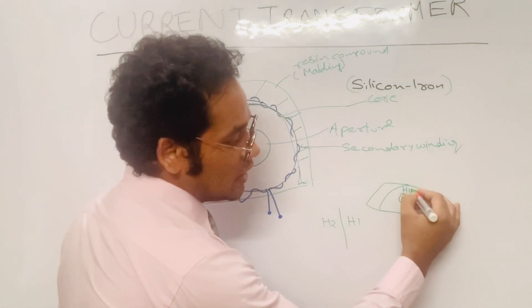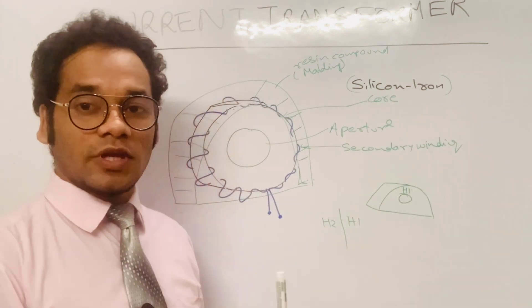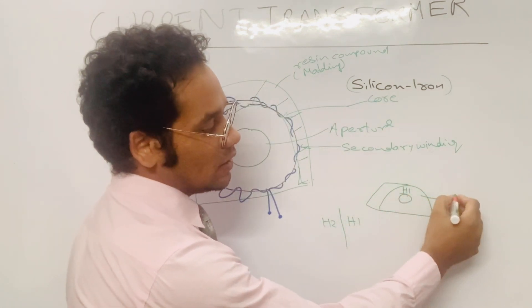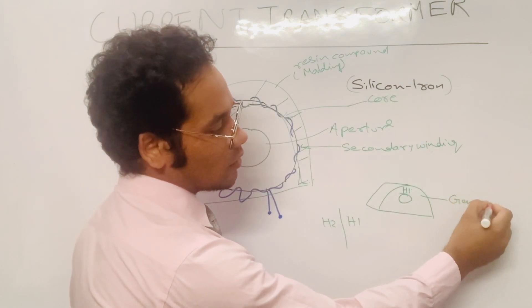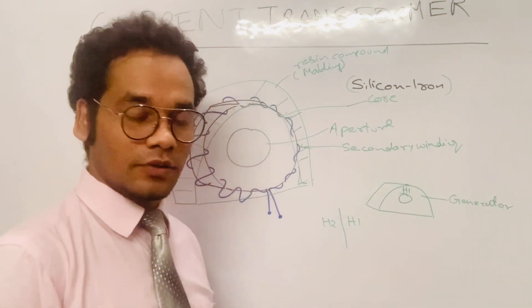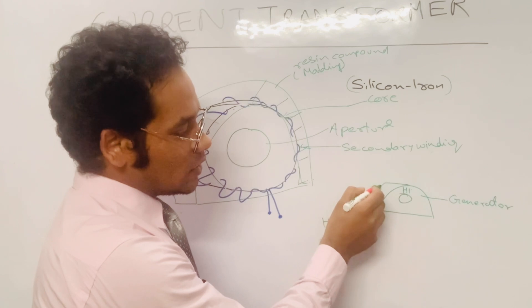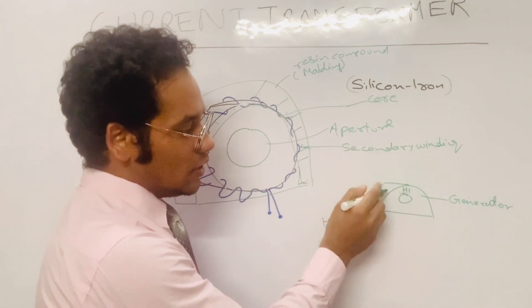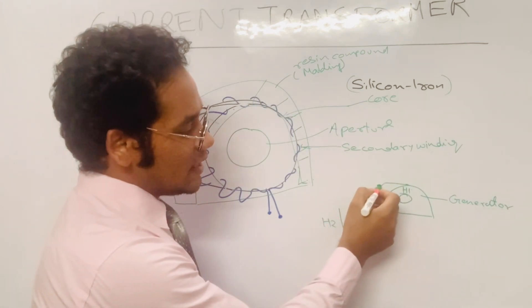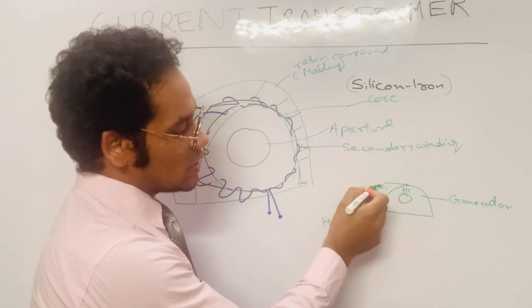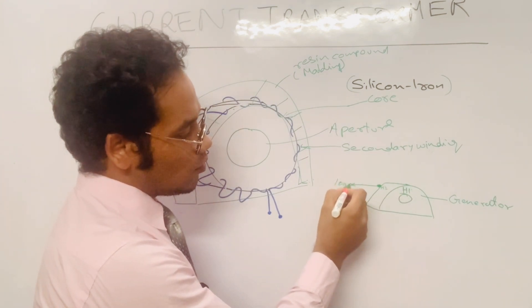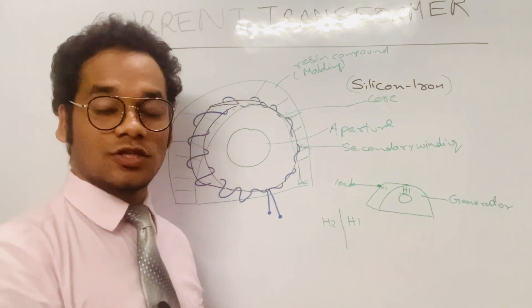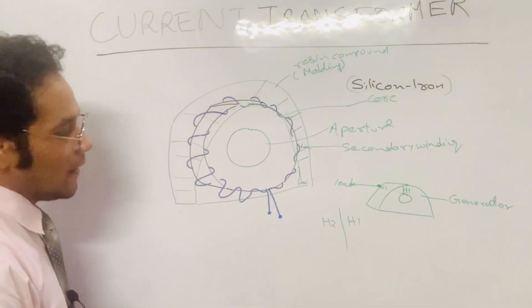H1 tells you that this is the side of the current transformer which should face the generator. The other face, H2, should be facing the load. So H1 faces the generator side and H2 faces the load side.